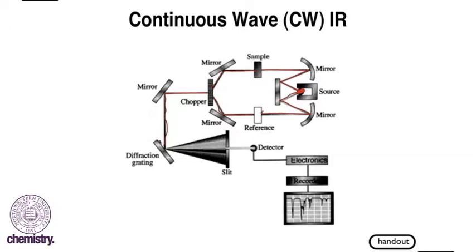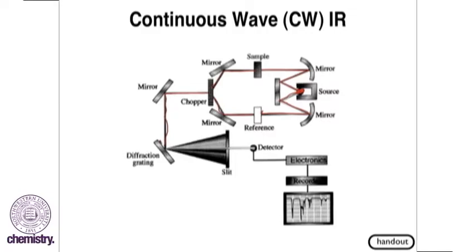In a CW-IR instrument, the diffraction grating is basically a series of filters. This is going to allow us to sample one wavelength at a time. We continuously vary the wavelengths we are analyzing with. That's where the name CW comes from.